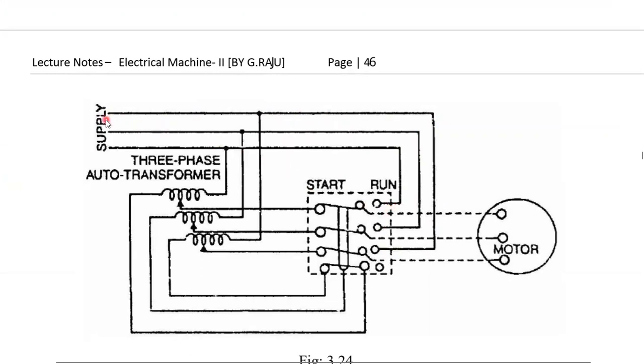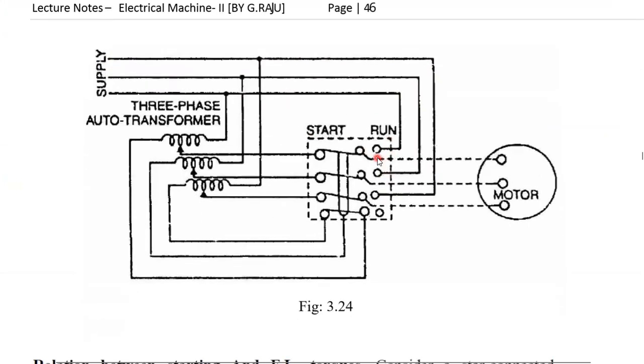Okay, this supply is connected to the run positions, and also the supply is connected to the start positions. These are the three connecting leads, with a switch in between. Okay, at the time of starting, these switches are closed at the start position, and they open at the run position. At the run position, these switches are open. That means the supply is fed to the induction machine.